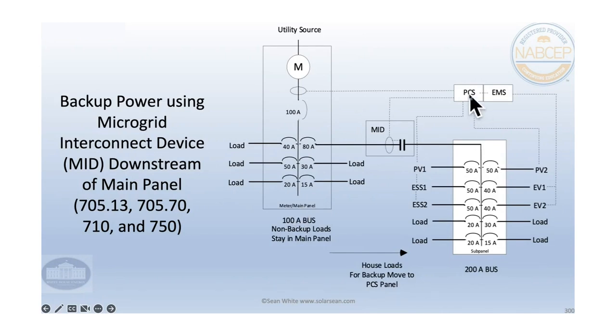There's the power control system where I was talking about 705.13. And so we can put CTs in different places, and then we can protect things without having to follow things like 705.12 with all the load side connections, 120% rule. So we can throttle things down by detecting the currents, making sure that we're not overloading this bus bar or this conductor. So we would not have to oversize this conductor because we can control all this PV and energy storage here. You can see we don't even have to put it at the opposite end of the bus bar. I just think you might as well, but you don't have to.